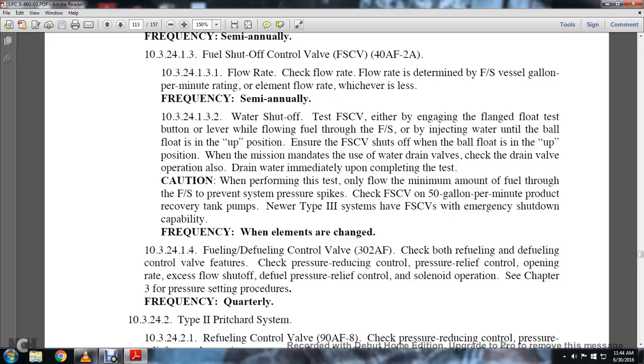10.3.24.14. The fuel defueling control valve, 30 in the model 302 AF. Check both refueling and defueling control valve features. Check the pressure reducing control, pressure relief control, opening rate, excess flow shutoff, defuel pressure relief control, and solenoid operation. See Chapter 3 for pressure setting procedures. Frequency for the fuel defueling control valve is quarterly.